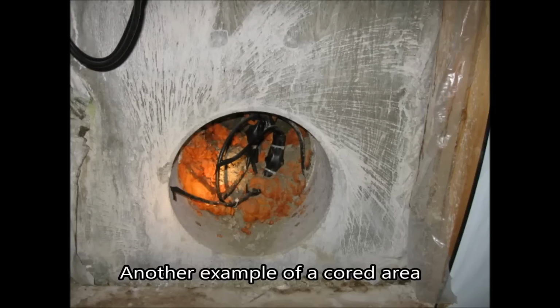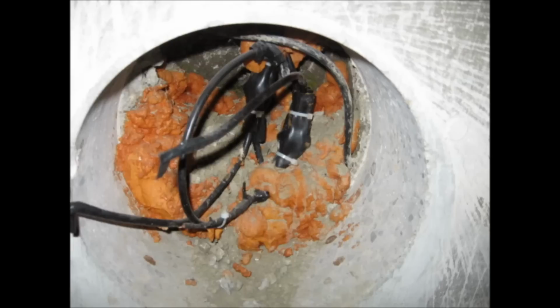Upon removing the core, an extreme hazard is exposed. As you can see, bare wires have been left unrepaired inside. The seller of this home had unknowingly purchased a grow-op house 18 months earlier, and this problem was discovered when they were trying to sell it. Sometimes the red flags are a cover-up attempt, like this concrete patch, or the unusual placement of a wall board underneath the electrical panel. Always look under the electrical panel if you are suspicious of a grow-op home.